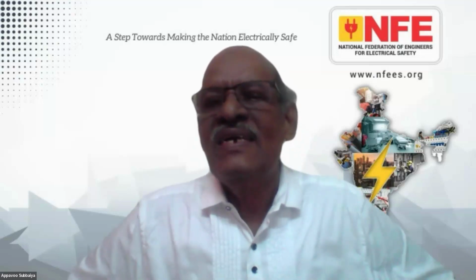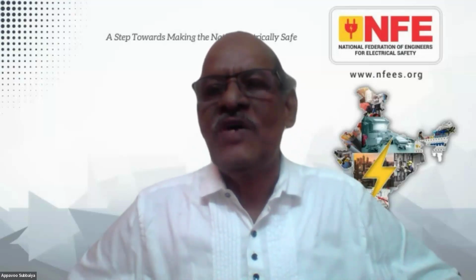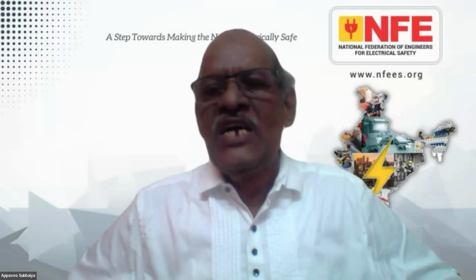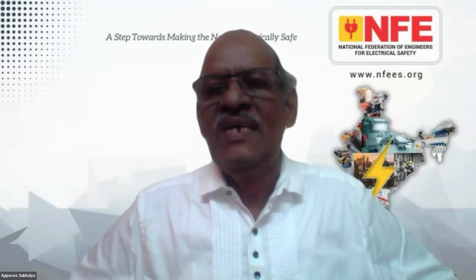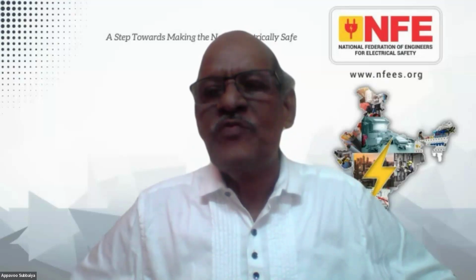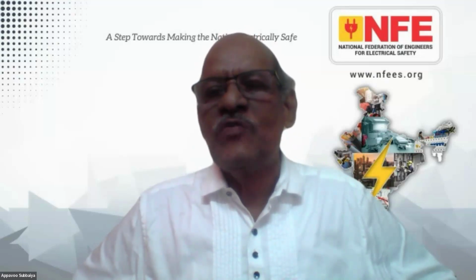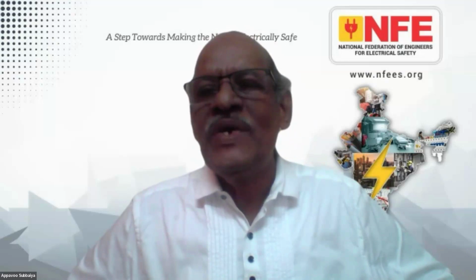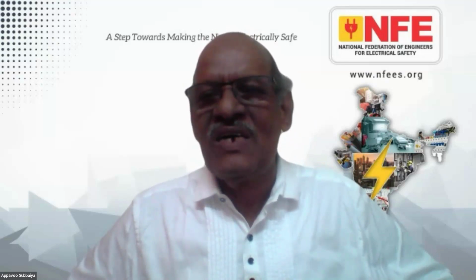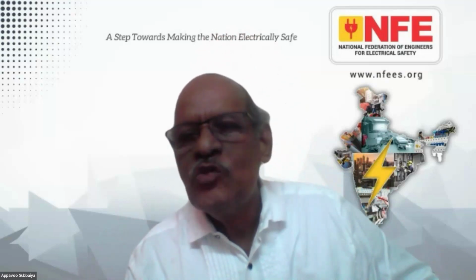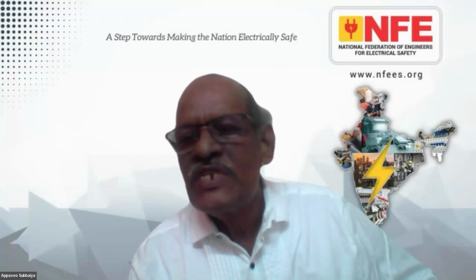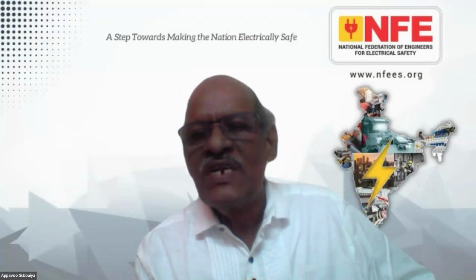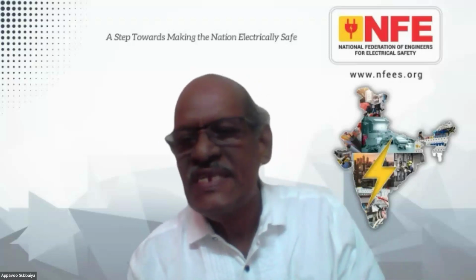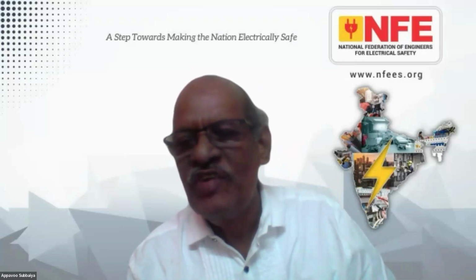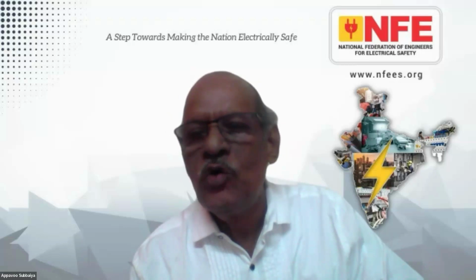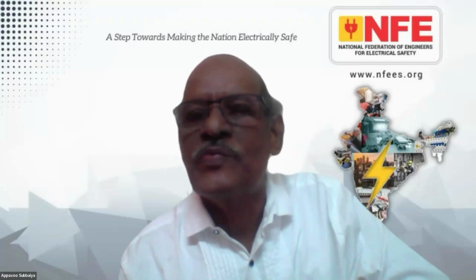Once you provide a neutral to earth connection with a TN-S system after the UPS, if there is an isolation transformer after the UPS and you provide TN-S right from that transformer, then there won't be any neutral to earth voltage. By a wrong connection, you are subjecting your downstream electronic devices' reference to another voltage. So this is the key. It is not about providing a number of earth electrodes. It is low frequency noise mitigation. You can go through our website.